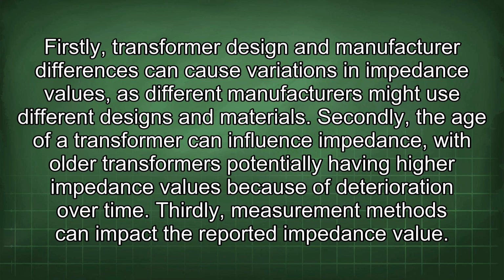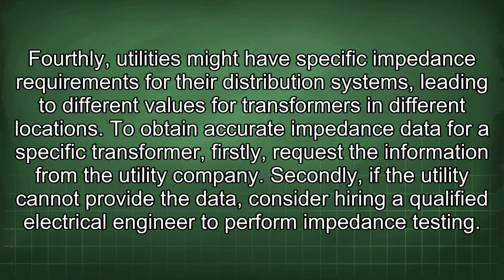Firstly, transformer design and manufacturer differences can cause variations in impedance values, as different manufacturers might use different designs and materials. Secondly, the age of a transformer can influence impedance, with older transformers potentially having higher impedance values because of deterioration over time. Thirdly, measurement methods can impact the reported impedance value. Fourthly, utilities might have specific impedance requirements for their distribution systems, leading to different values for transformers in different locations.